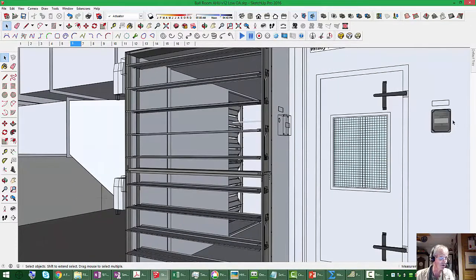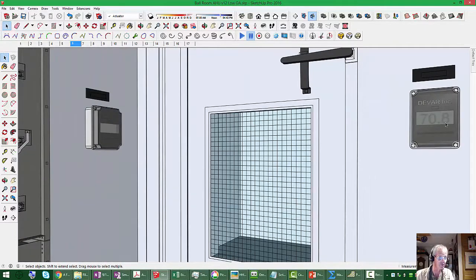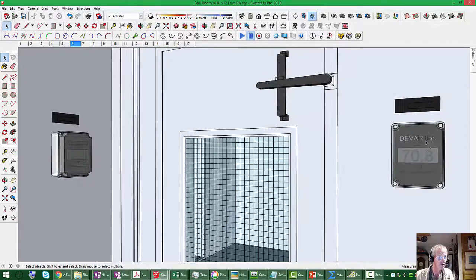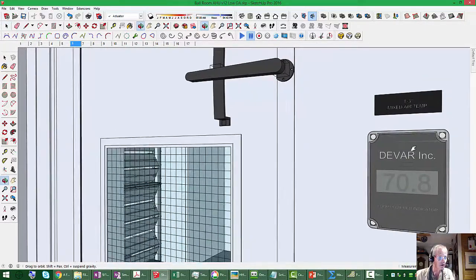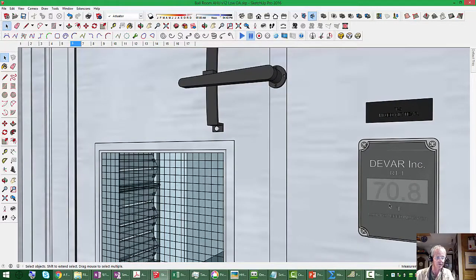And in fact, here's a sensor right here. It turns out that's the mixed air sensor, right? Yeah, and it says that the mixed air temperature is 70.8. So it looks like so far, we're taking 70.8 degree air and cooling it down to 52 degrees with chilled water. That's an unnecessary load. So there's part of the mystery load on our chilled water plant.